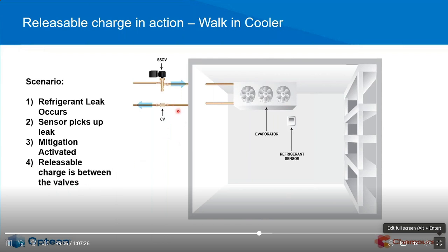So if leak detection senses it, it's going to go into mitigation strategies. That could be just the isolation or the cubic feet in the box itself, or it could be the fans come in on lesser charges on what would be your doors and drawers, and then the larger one where you have to bring mechanical ventilation in.